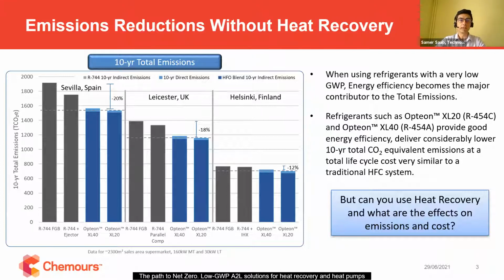Here's a summary of the previous study, comparing three different cities—Sevilla, Leicester, and Helsinki—with different refrigeration system architectures for a supermarket. Focusing only on CO2 technologies, flash gas bypass, or the best amelioration to the CO2 system depending on geographical area, compared to Opteon XL40 or XL20, we see that Opteon refrigerants can provide between 12 and 20% reduction in total emissions compared to CO2 across all the different climates in Europe.